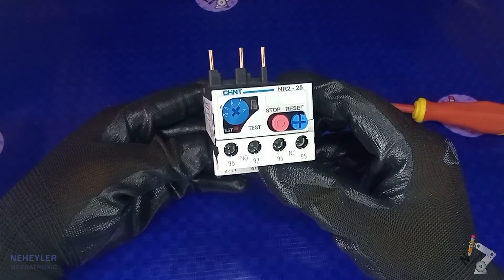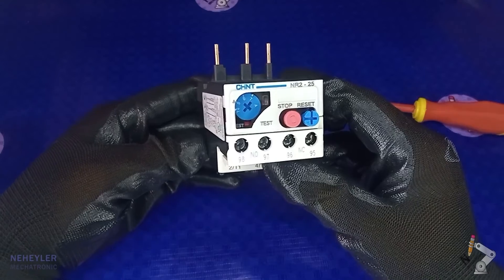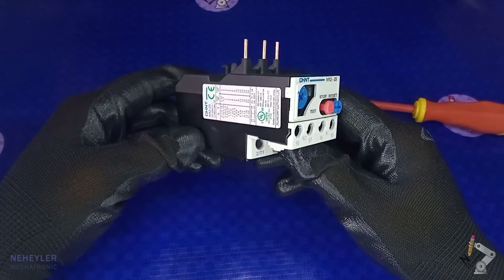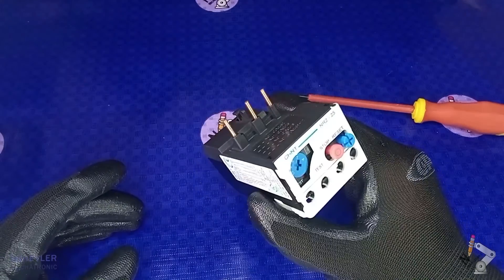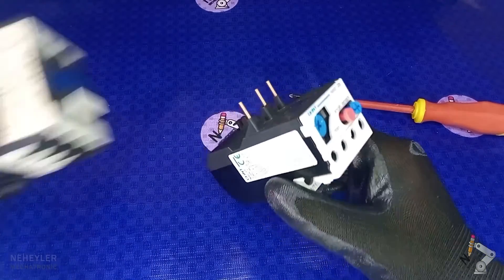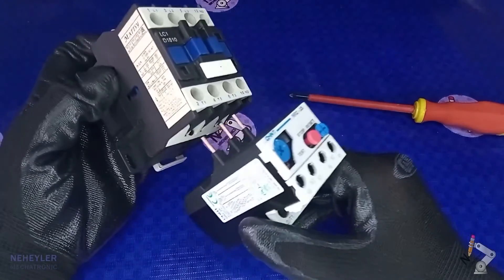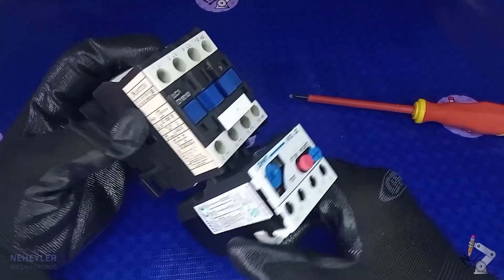The thermal relay is an electromechanical device that provides protection functions for single-phase and three-phase motors against possible overload or overheating in the motor winding. This device by itself does not have cutting power, so it needs another device, which is the contactor, which can cut the current between its main contacts.